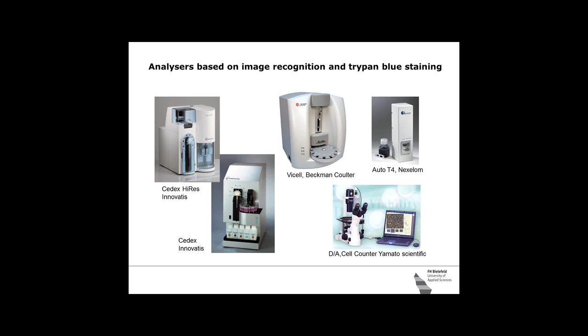And what do these systems do? They automate the process of staining. They transfer the stained sample into a flow cell, and a microscopic image is taken from those samples. So the analysis is based on the same information as the manual trypan blue cell counting, and the image is recorded with a CCD camera and then automatically analyzed by an image recognition software. So the whole process is automated and it is very transparent, and that's important.